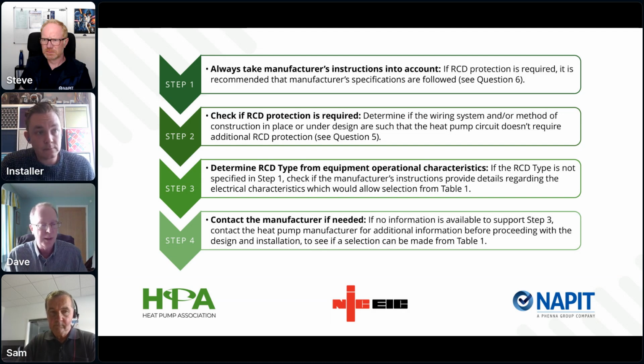Partly that comes from heat pumps being international products. So manufacturers will make a product for the whole of Europe or beyond, and will put a statement in their manufacturing instructions saying follow local wiring regulations. So then you have wiring regulations saying take account of manufacturer's instructions, and manufacturer's instructions saying take account of the wiring regulations, and you still haven't got an answer. Potentially, that's a situation. Or they might say fit a suitable RCD, and then it still comes back to the designer to make that selection.